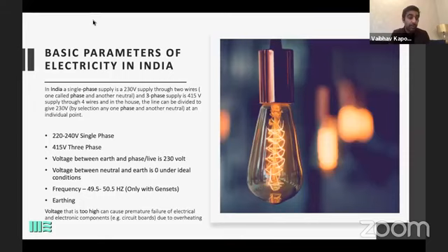These parameters have to be adhered to for each piece of equipment. Regarding the voltage between earthing and phase, if you put a multimeter on the earthing side, the metal body which is always earthed, and then on the phase, red, yellow, or blue, you should get 230 volts, meaning the earthing is proper. The voltage between neutral and earth, the black wire and the earth wire, the green wire outside that box, should read 0. Under ideal conditions it may go up to 0 to 5 volts, which is acceptable.